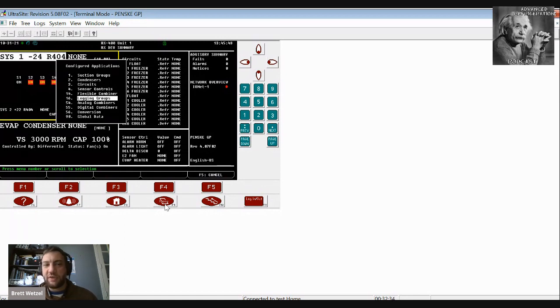But then you want to log something that's maybe a little bit longer, like maybe you might log a liquid level control, basically just see your liquid level, graph it every half an hour, every hour, and then utilize that to get maybe a 365 view, maybe a whole year. So you can see the ups and downs, see if you have leaks in the system. Analog combiners, basically taking analog values and combining them, whether it be min, max, you can minus some values. Same thing with digital combiners. Basically, it's taking a digital value.